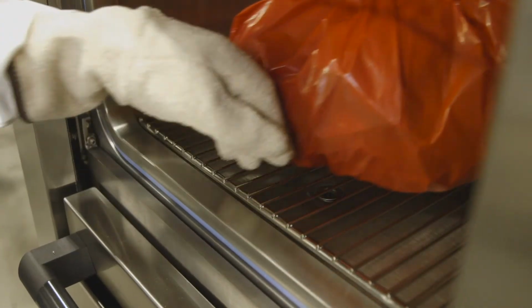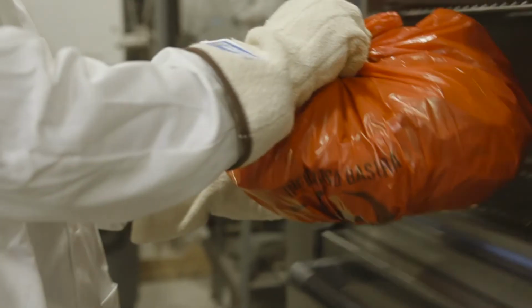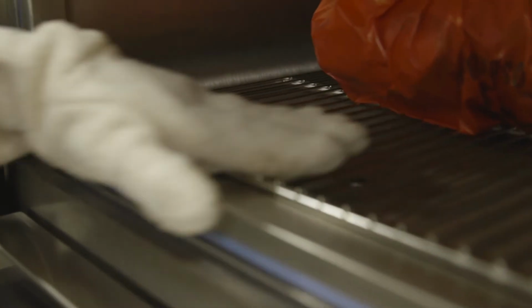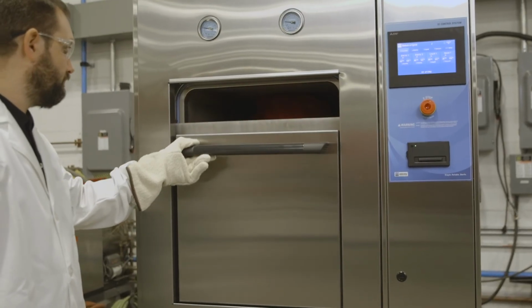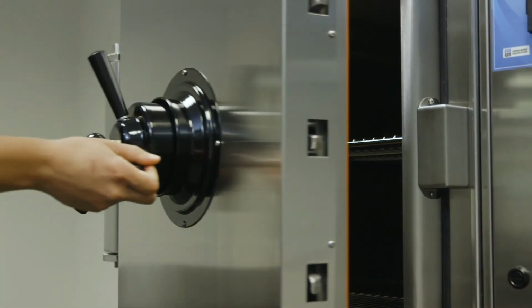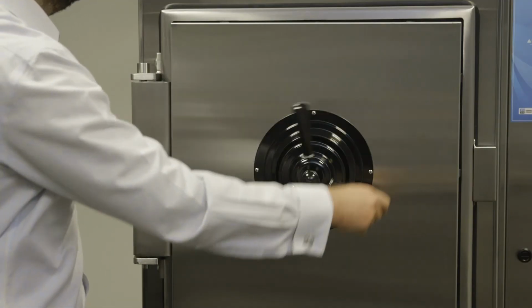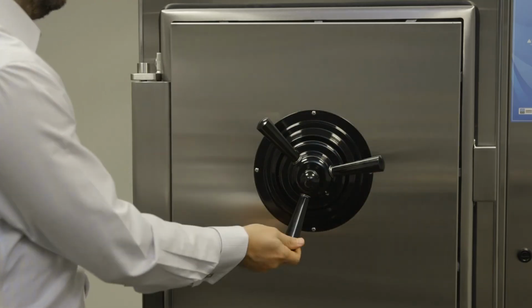This prevents steam from circulating through the chamber. If the autoclave has a metal wire rack shelf, place the items so that they are easily accessible from the autoclave door. Lastly, make sure that the chamber drain is not covered and steam and condensate can flow freely to the chamber drain. Once the unit is loaded, close the autoclave door. If you're using a hinge door autoclave, close the door fully, engage the locking pins, and turn the locking mechanism until it stops moving. In this case, we're operating a vertical sliding door sterilizer. In either hinged or vertical door design, the door and locking mechanism should only take a minimal amount of force to operate. If the door is not completely shut, the control system will alert you on the screen.